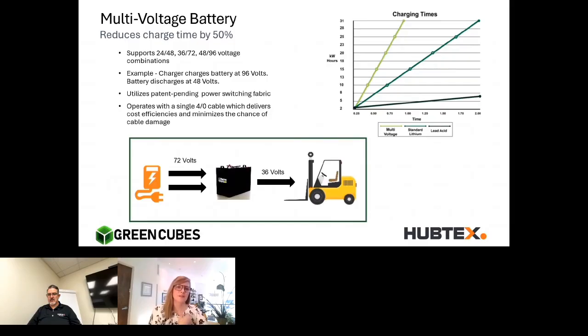Specific to green cubes, we have something called a multi-voltage battery that can increase or decrease charge time by about 50%. It sounds a little confusing, but basically you keep constant power on the discharge and charge: you charge at double the voltage and half the current, and discharge at double the current and half the voltage. So it's constant power, meaning you could charge a full 48 volt battery at 96 volts and halve the charge time. It also decreases the size of cables required for charging, if you're using cables, which you probably wouldn't for an AGV, but it's worth pointing out anyway.